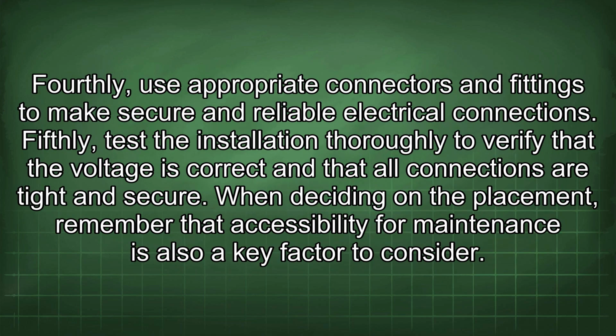Fourthly, use appropriate connectors and fittings to make secure and reliable electrical connections. Fifthly, test the installation thoroughly to verify that the voltage is correct and that all connections are tight and secure. When deciding on the placement, remember that accessibility for maintenance is also a key factor to consider.